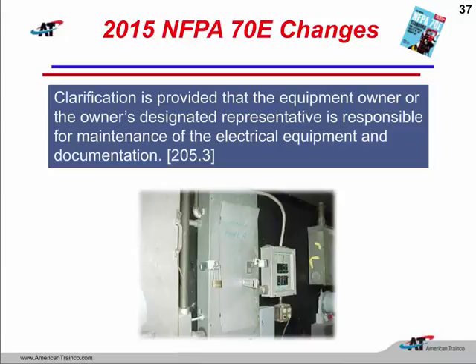In conjunction with this, we should understand that the National Electrical Code, which is NFPA 70, and NFPA 70E, which is the safety document we're talking about now, go hand in hand with NFPA 70B, which is electrical maintenance for our electrical equipment. And the new revision of NFPA 70B wants us to have another label on our equipment. And that label is going to be a reflection of whether the equipment has been maintained properly over the years.